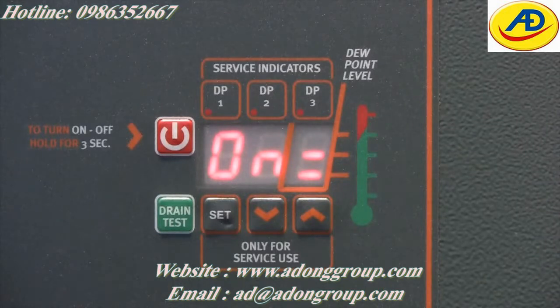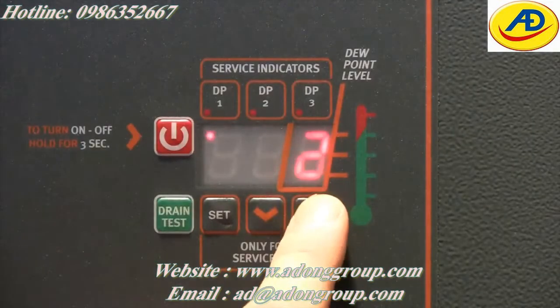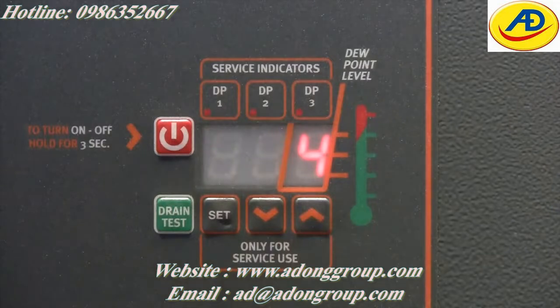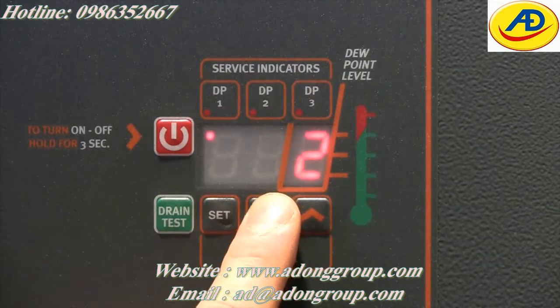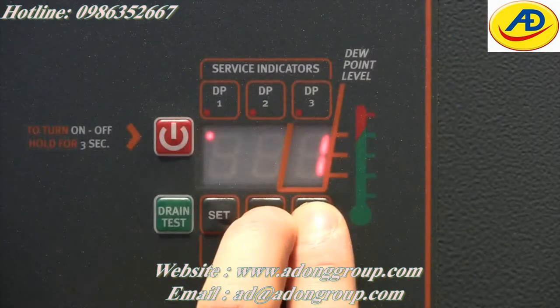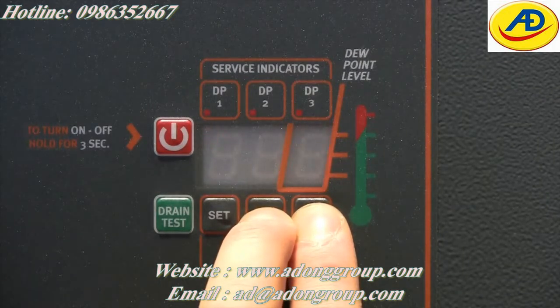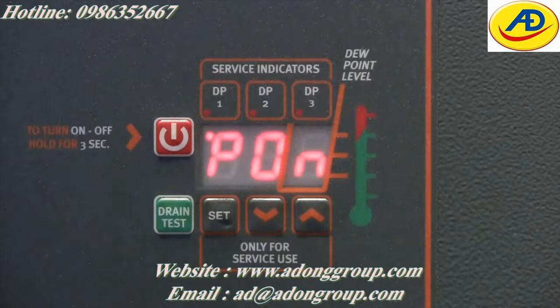Before unlocking the unit, ensure the readout shows the dew point of the unit, and not values for C8 or C9. Pressing the buttons while the value for C8 or C9 is still showing will adjust these values, something not to be done. To unlock the board, press the up and down keys simultaneously for 10 seconds. Wait for the code PON to appear and then release.